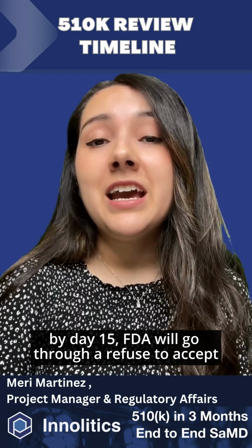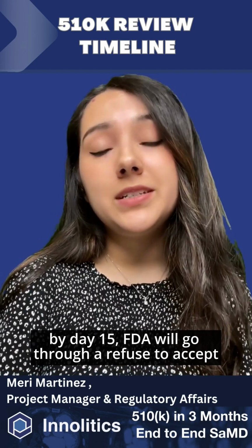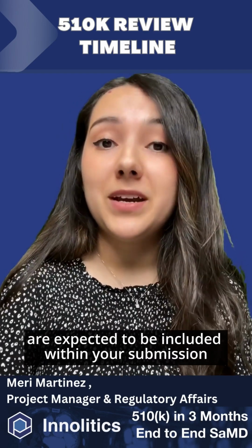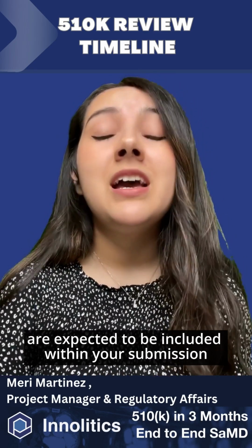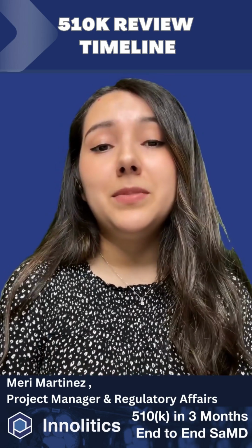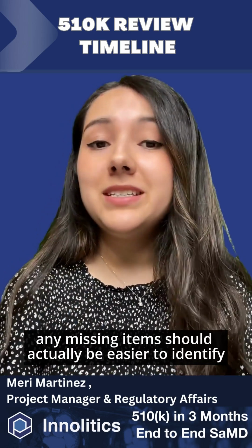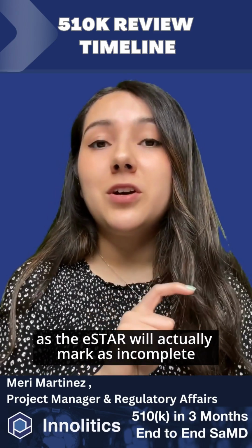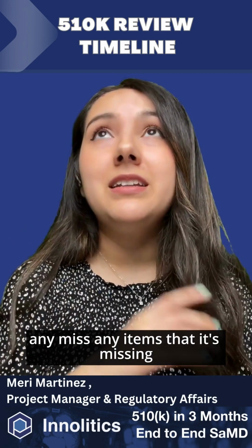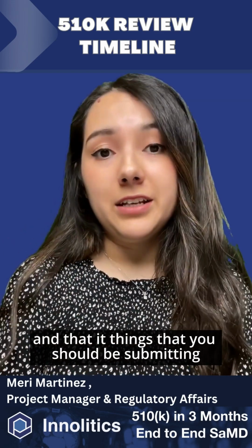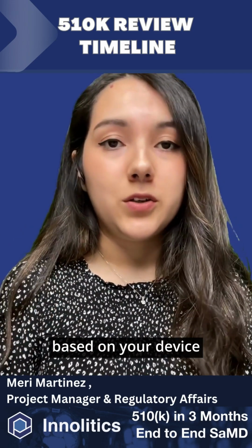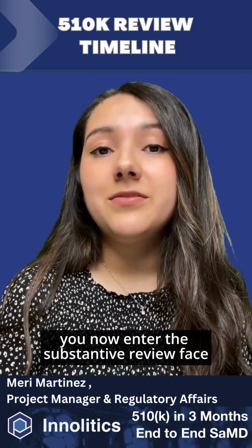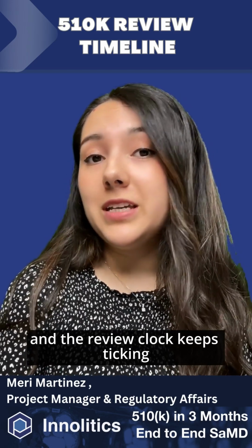By day 15, FDA will go through a refuse to accept or RTA checklist to ensure that all the items that are expected to be included within your submission have in fact been submitted. Please note that with the eStart, any missing items should actually be easier to identify, as the eStart will mark as incomplete any items that it's missing and that it thinks that you should be submitting based on your device. If your submission passes RTA, you now enter the substantive review phase, and the review clock keeps ticking.